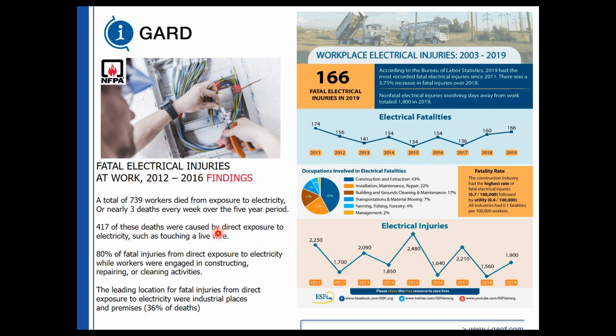417 of these deaths were caused by direct exposure to electricity, such as touching a live wire. Again, we reiterate, a lot of the injuries are occurring after we put on the PPE and we're performing the absence of voltage test. We saw this from the graphic we had earlier. The leading location for fatal injuries from direct exposure is industrial places and premises, 36% of deaths. People are getting hurt. Traditional methods that we've used in the past are not good enough anymore.